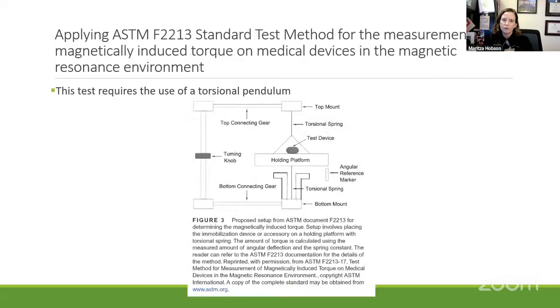Okay. So then this is determining the measurement of the magnetically induced torque, which requires the torsional pendulum shown here in this figure. These were all recreated from ASTM documents with permission. Not all centers or even universities have this type of system. It's pretty complex, right? And there probably isn't going to be one made out of MR conditional or MR safe materials. So that underlines our recommendation to get devices where the MR safety status is already determined.